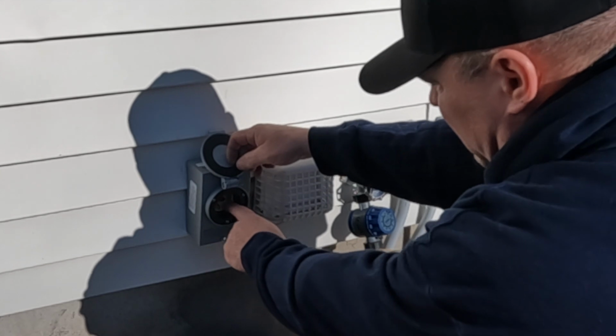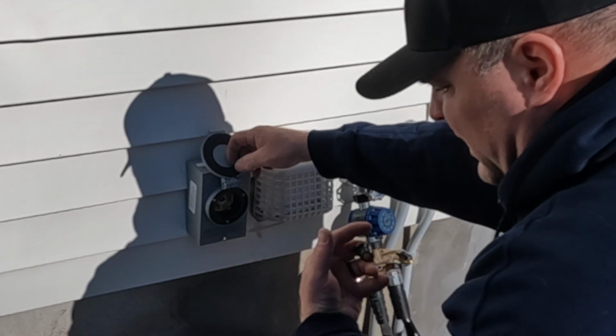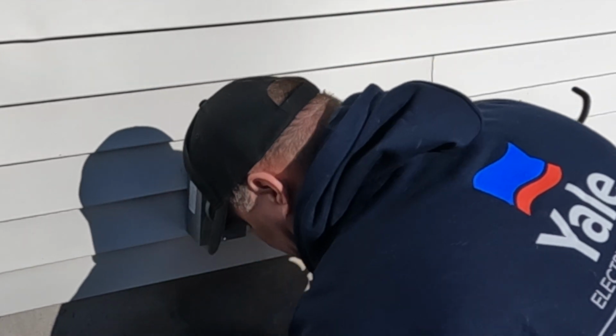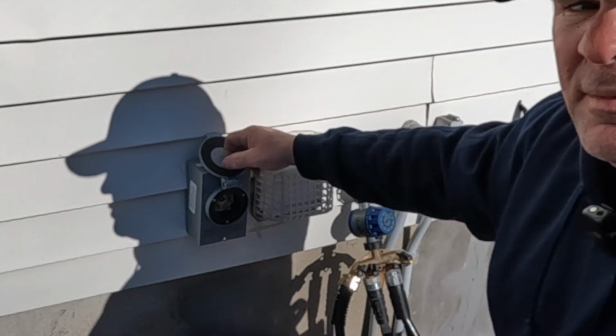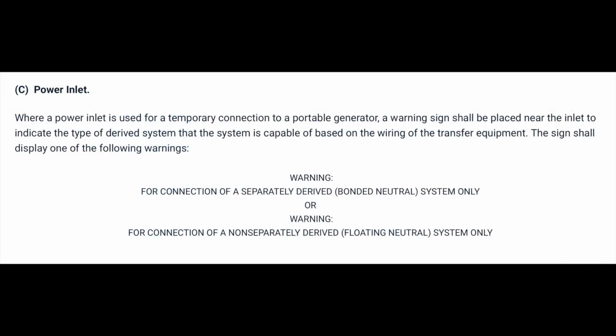It's got a locking, it's an inlet because the prongs are sticking out versus an outlet, which would be the female end, if that makes sense to you. I hope it does. When you use a power inlet like you see in the video, you have to abide by these rules right here. Where a power inlet is used for a temporary connection to a portable generator, a warning sign shall be placed near the inlet to indicate the type of derived system that the system is capable of based on the wiring of the transfer equipment. The sign shall display one of the following warnings.